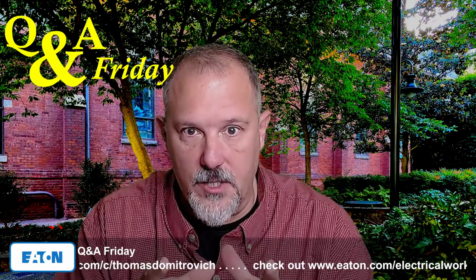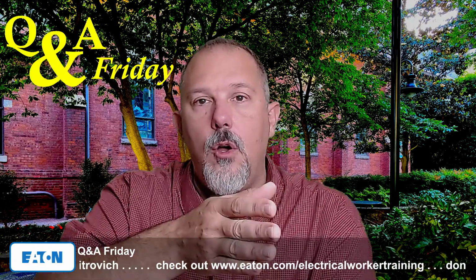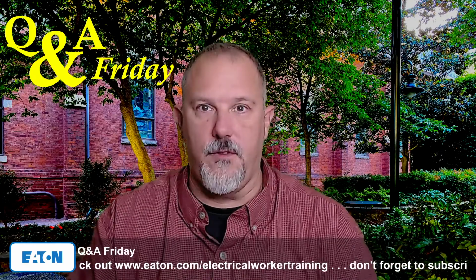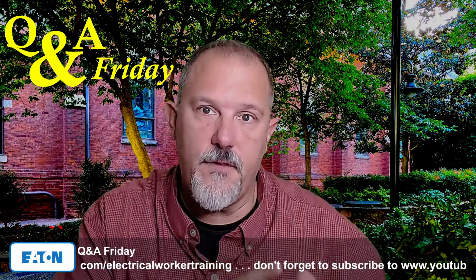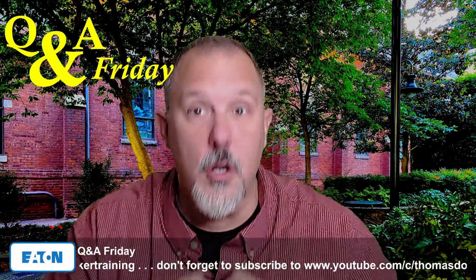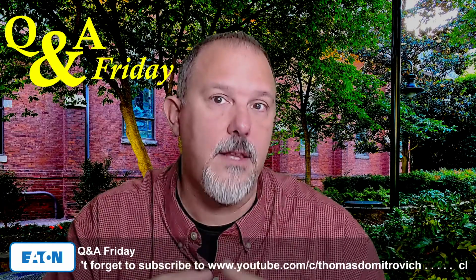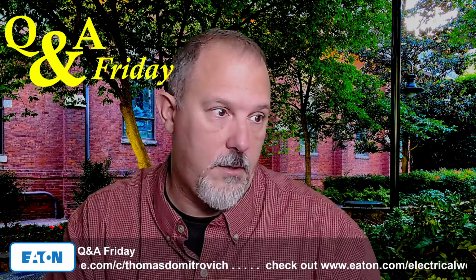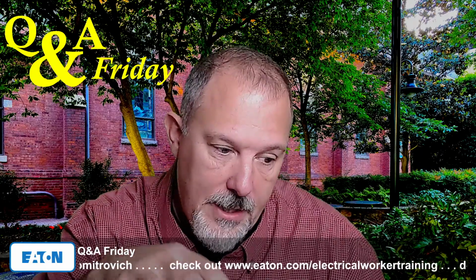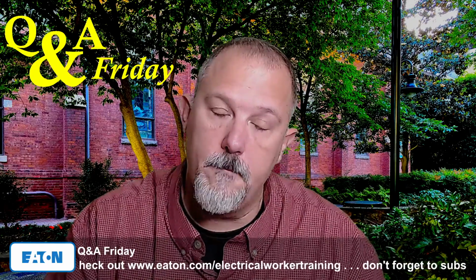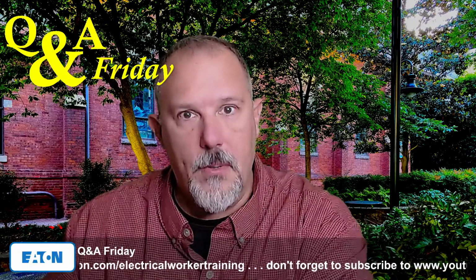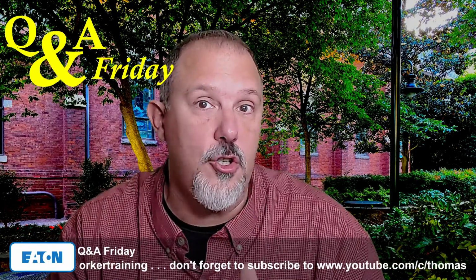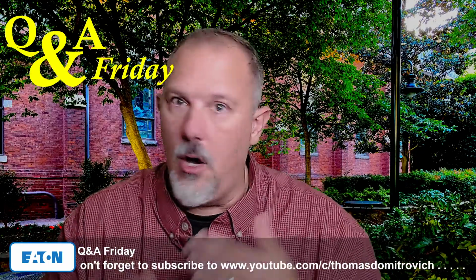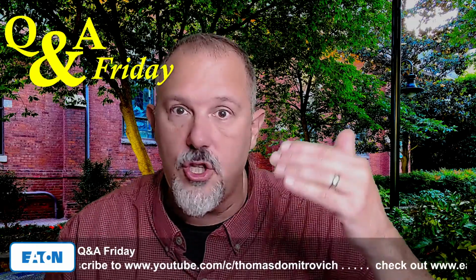So here's the thought process on that. We have torque specifications for overcurrent protective devices, right? If my overcurrent device has the ability to hold the contacts closed for 30 cycles, the torque on those terminals reflects the testing at those levels of fault current at those clearing times. That's why it's very important that you follow the manufacturer's instructions on torque. So the torque on all of the individual products for the terminations, and the guidance on what size conductors you can put and how many conductors you can put under those lugs, all of this plays a role, whether it is a 30-cycle device or a 2-cycle device, a 4-cycle device. We test it under those scenarios.